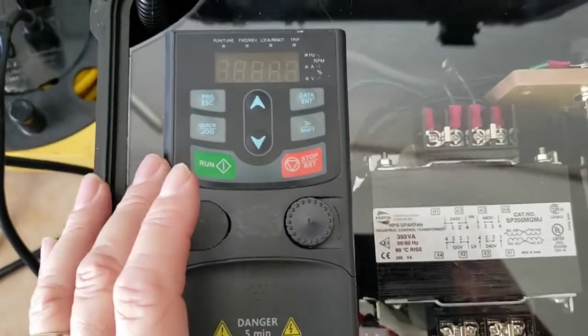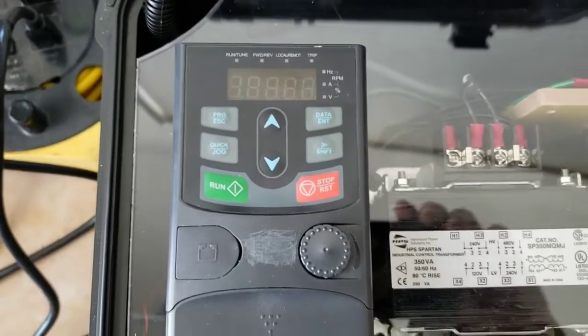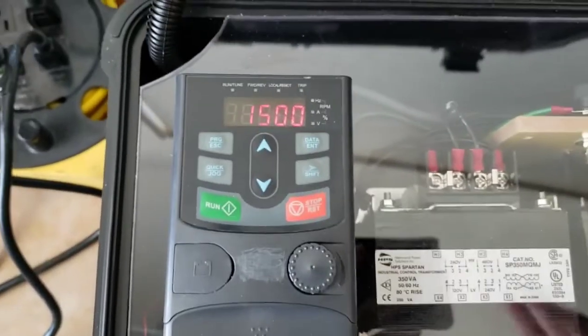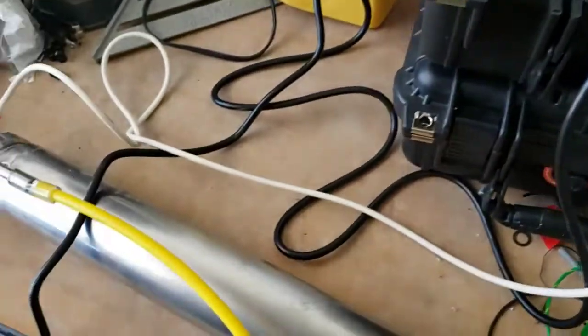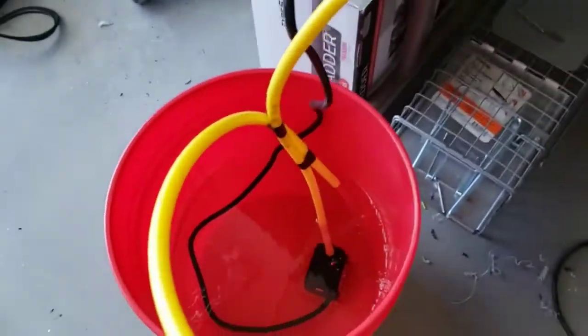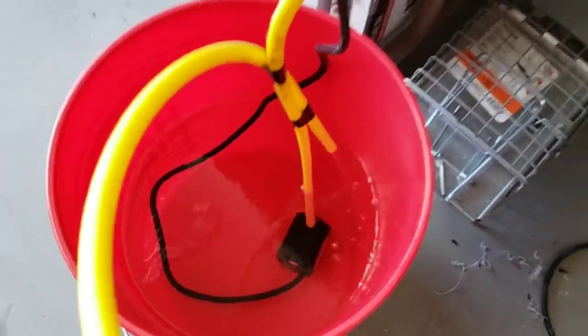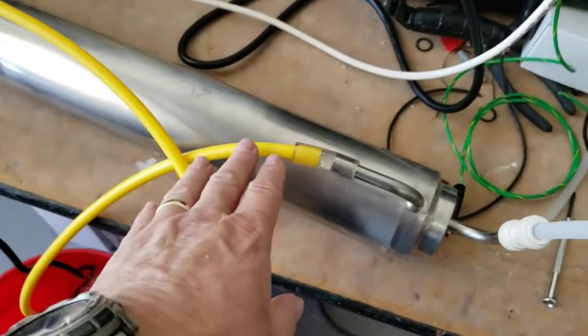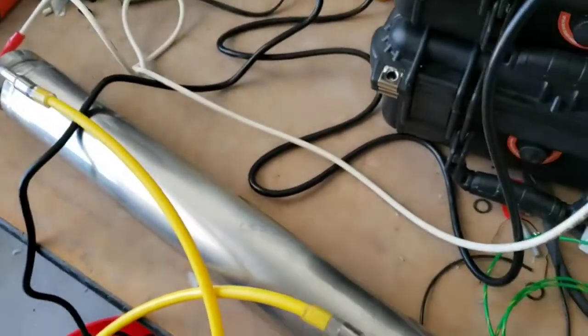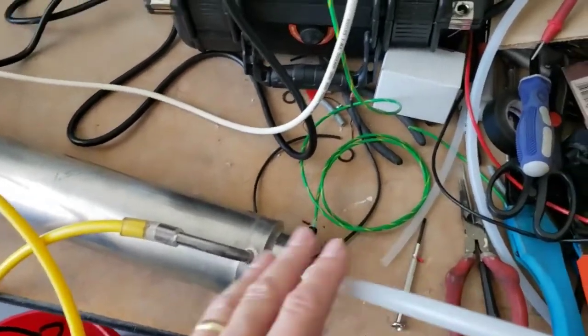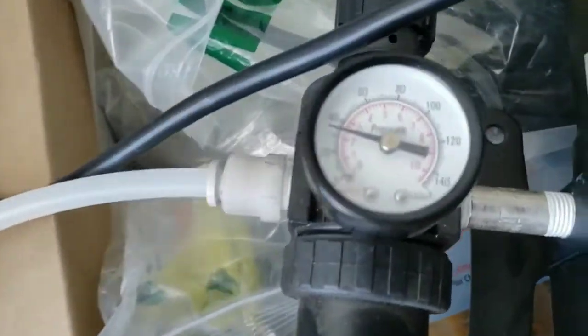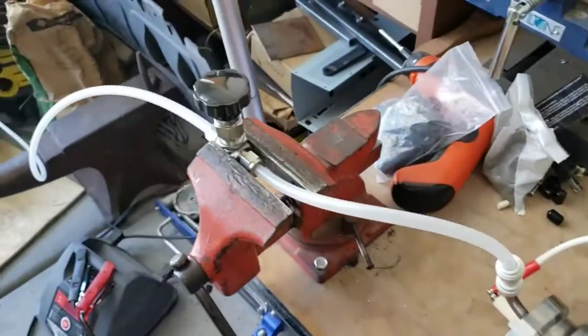Let me hook up the air, and I'm going to do a demonstration going through this sweep. Okay, so I just hooked up air to my dryer. Pardon the mess, I'm doing this in my laboratory. I do have a little fountain pump just running some cooling water through this, but in a short test in the field, you don't necessarily have to have cooling water on, but you do need to have it purging with gas at normal cell pressure. I've got this one at about 35 psi, and flow rate isn't that important. I've just got a very low flow rate.